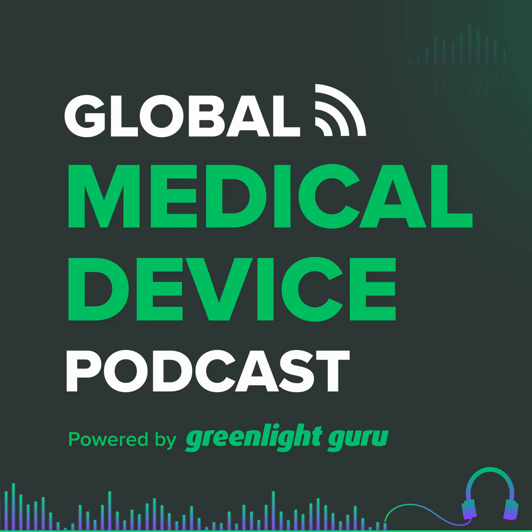But taking the 14971 top-down approach, you're looking at, what are the most serious things that could happen from this device? The top one is going to be giving too much insulin. And so at that point, you're looking at, how can we mitigate a user getting too much insulin? And that's built into my controller, actually, too. I'm not allowed to give myself more than 10 units at a time.